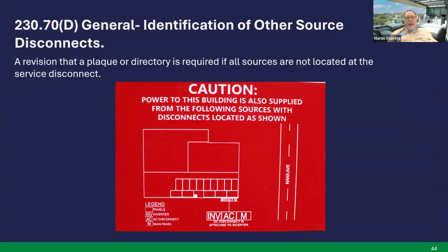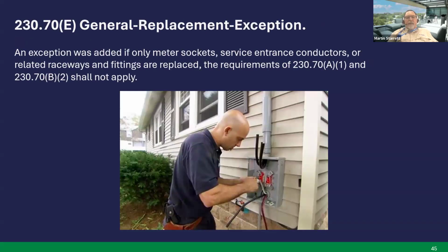230.70(D), identification of other source disconnects. A revision that a plaque or directory is required if all sources are not located at the service disconnect. Next slide. General replacement exception. There's an exception that was added. If only meter sockets, service entrance conductors, or related raceway and fittings are replaced, the requirements of 230.70(A)(1) and 230.70(B)(2) shall not apply. So if you're replacing just only those parts, the disconnect requirements would not apply.